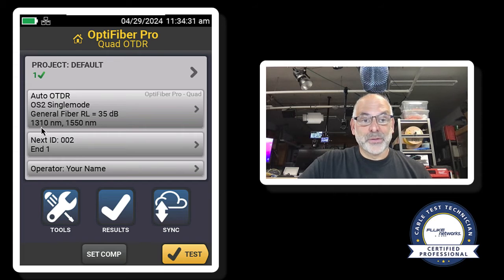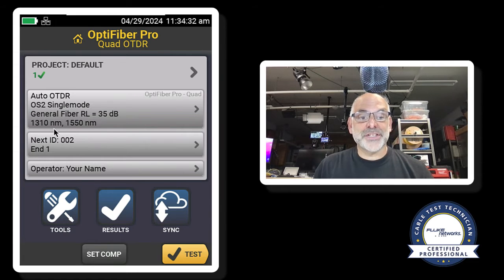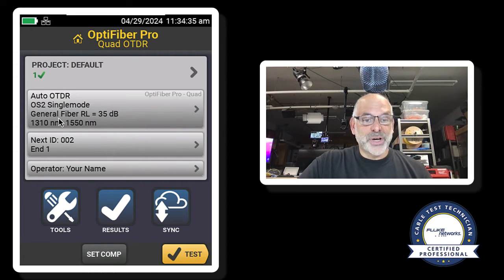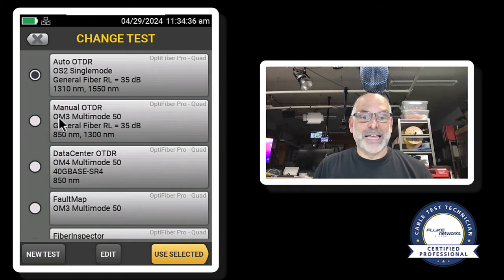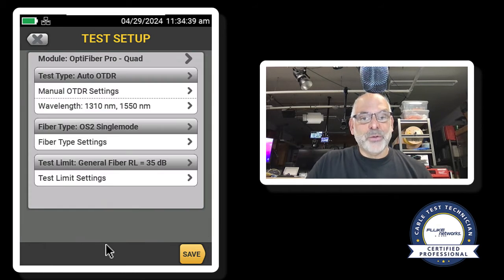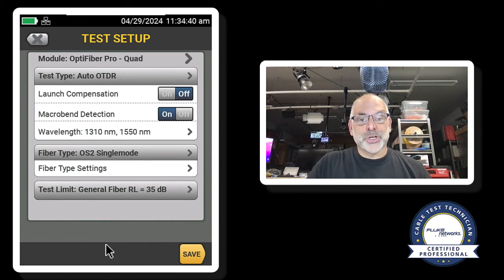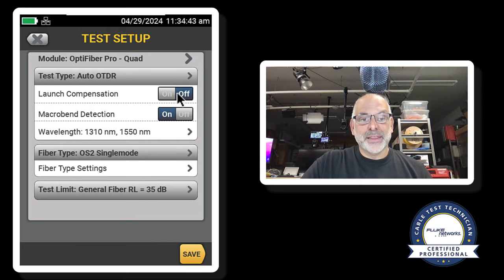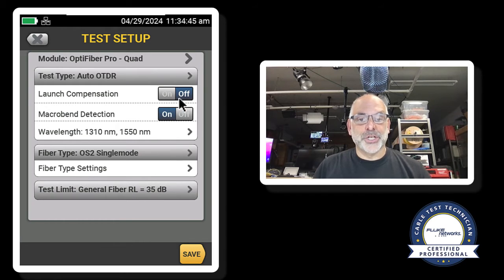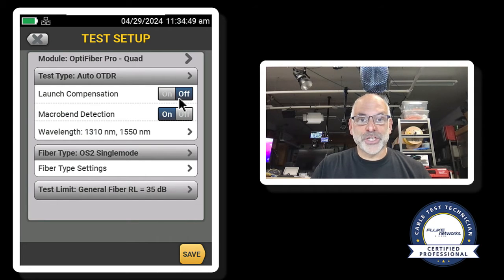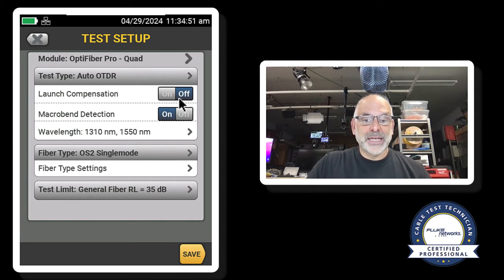And we're going to be testing at 1310 and 1550. So I'm going to tap on that, and I'm going to come in to edit. And what I want to make sure of is that my launch compensation is turned off. I want to make sure that launch compensation is off.